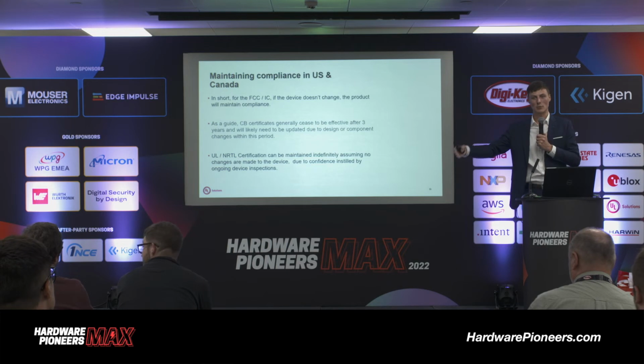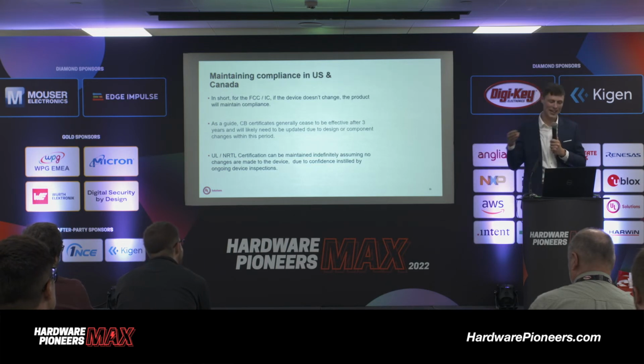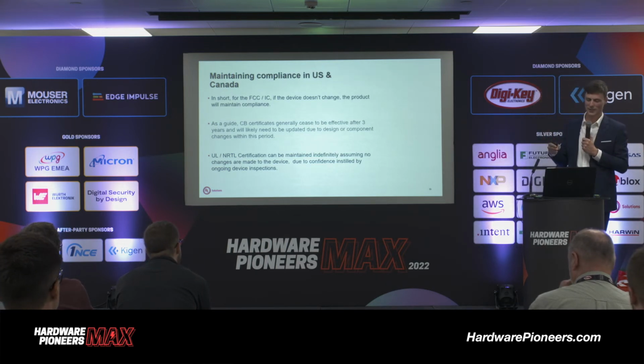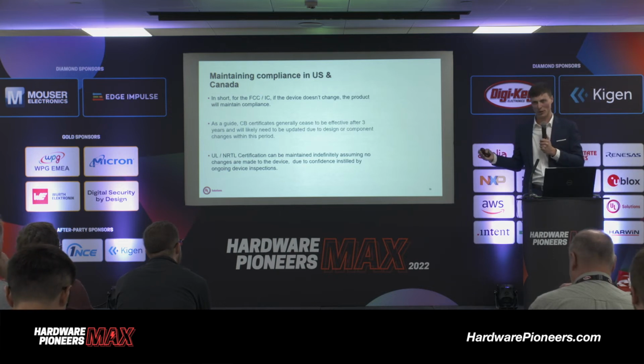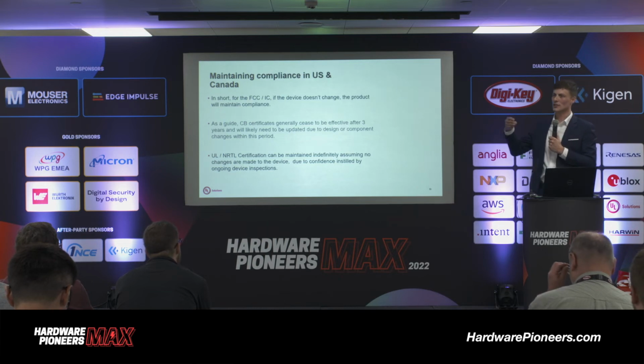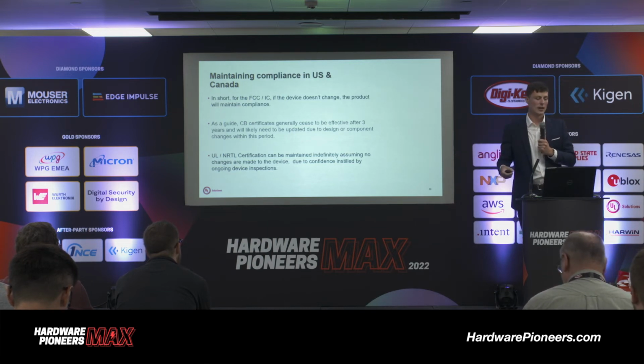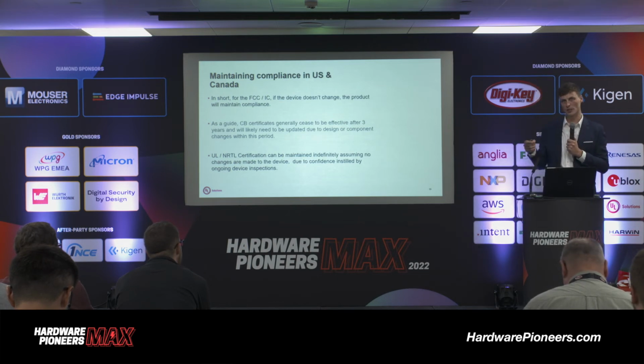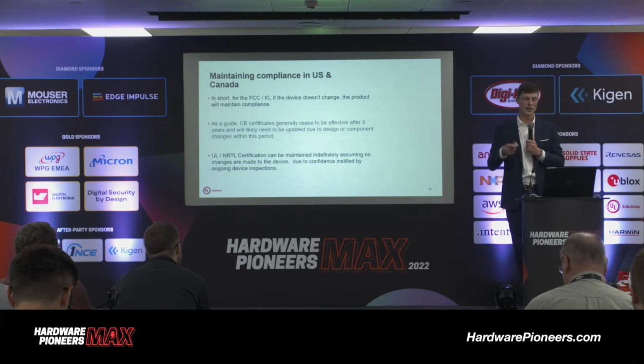Nationally recognized test laboratory. So when it comes to the UL mark, we wrote the standards as a not-for-profit part of our business, 120 years old, but there are other NRTLs available. Not that you'll hear me talking about them too much. Shortly put, we're looking at the US and the Canadian requirements there. Interestingly, with the UL mark, if you have your device certified to an older version of the standard, because part of holding a UL or an NRTL mark is that you have manufacturing location inspections of that device.